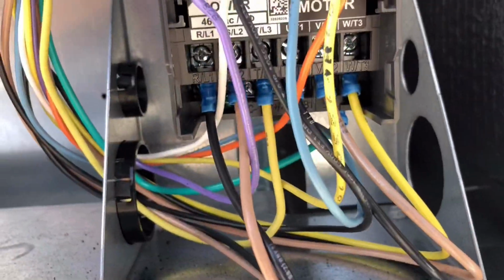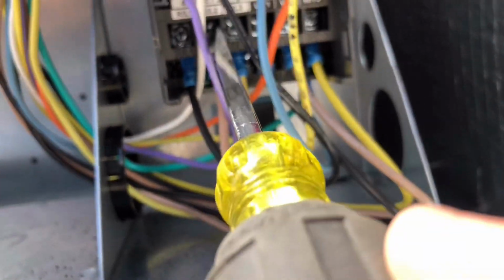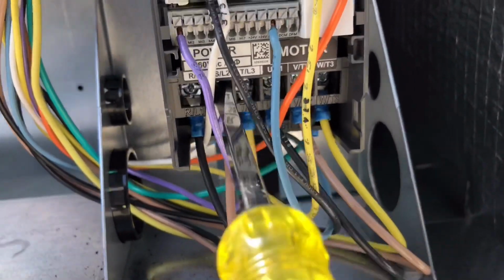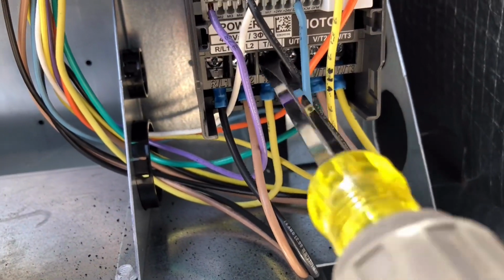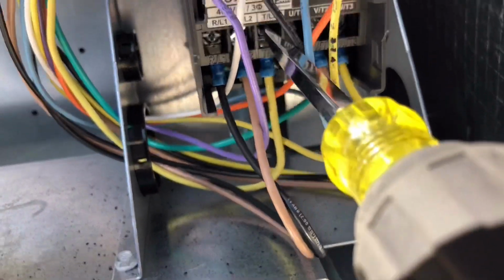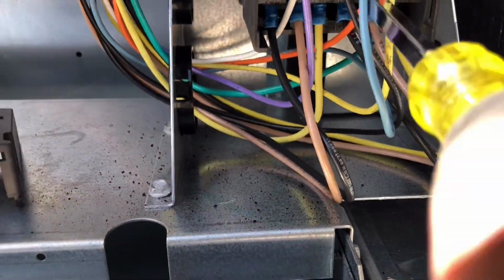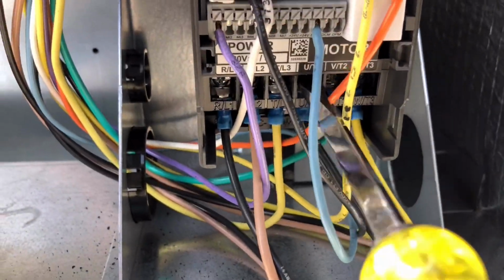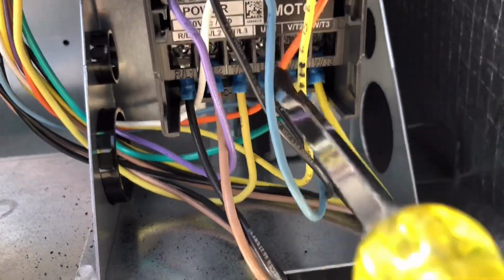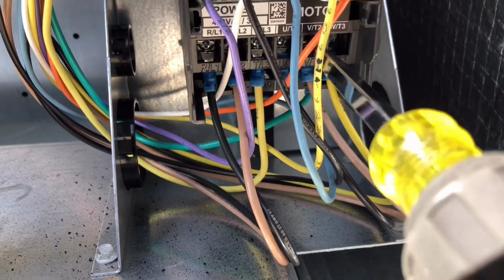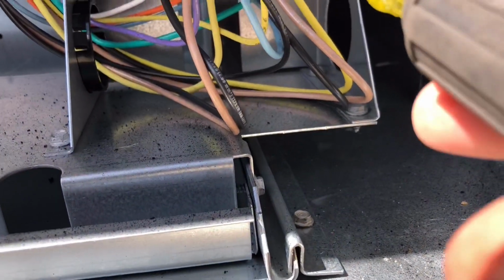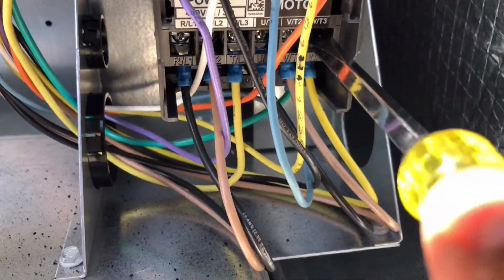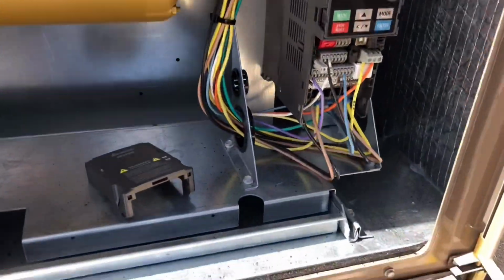I found this on several other VFDs. Is when you go to tighten it, you sometimes get a half a turn or so. Let's put a little bit of a quarter turn right there. Look at this one. See that? That was about a full turn right there. I don't know if that's what the code means. This one's tight. Let's see this one right here. That one's tight. So I had to just tighten about 3 of these.